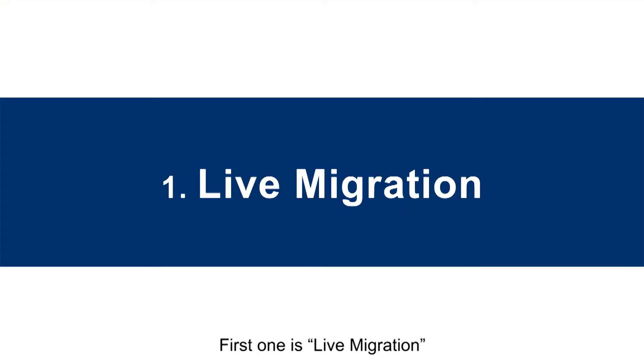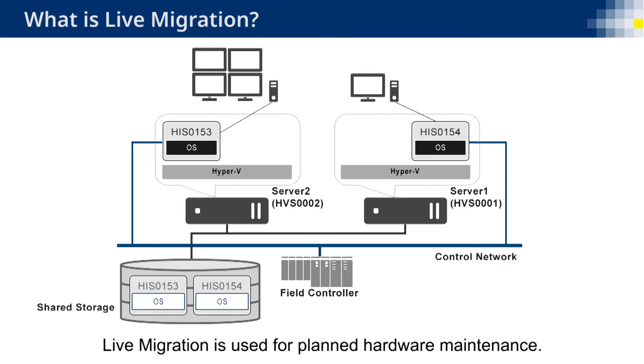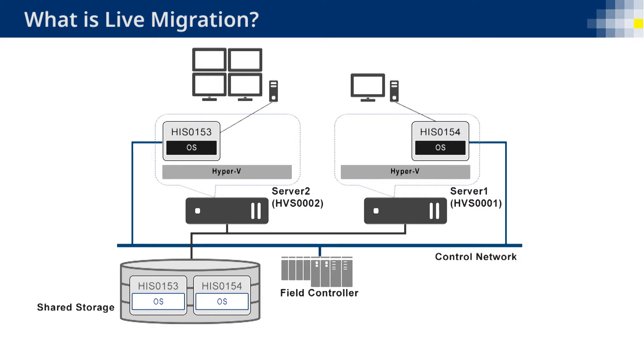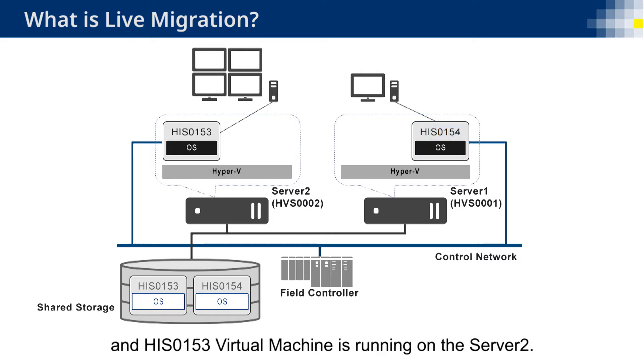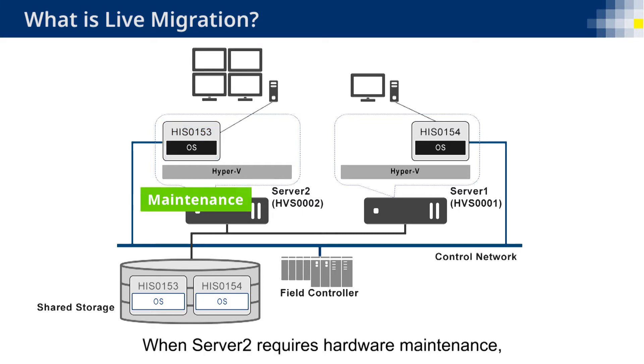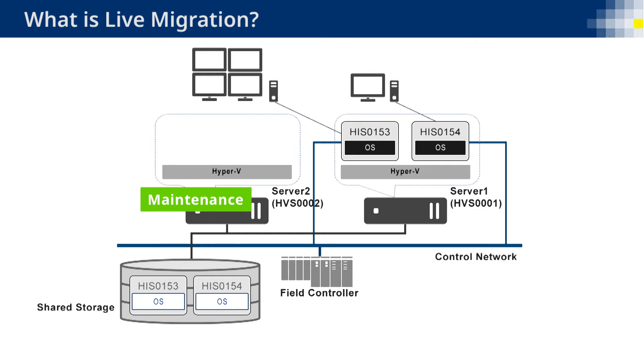The first one is live migration. Live migration is used for planned hardware maintenance. It moves running virtual machines to another virtualization server without stopping operation and monitoring. In this demonstration, HIS0154 Virtual Machine is running on Server 1 and HIS0153 Virtual Machine is running on Server 2. When Server 2 requires hardware maintenance, HIS0153 can be moved to Server 1 by live migration. Live migration will take only a few seconds, and plant operators may not notice it. With live migration, hardware maintenance can be done without affecting the plant operation.